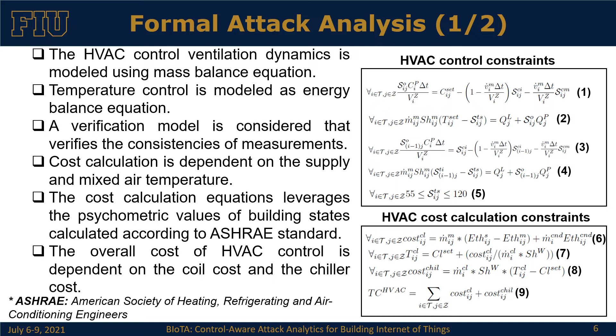The cost calculation is basically dependent on the supply and mixed air temperature. Cost calculation equations 6, 7, 8, and 9 use psychrometric values based on the American Society of Heating, Refrigeration, and Air Conditioning standards. The overall cost of HVAC control mainly depends on the coil cost and the chiller cost.